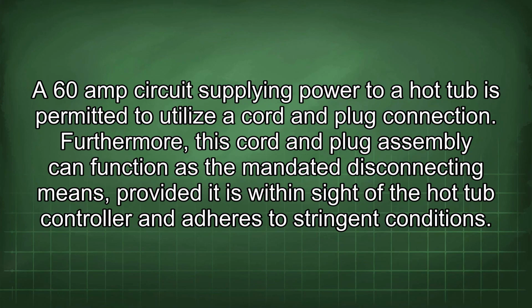A 60 amp circuit supplying power to a hot tub is permitted to utilize a cord and plug connection. Furthermore, this cord and plug assembly can function as the mandated disconnecting means provided it is within sight of the hot tub controller and adheres to stringent conditions.